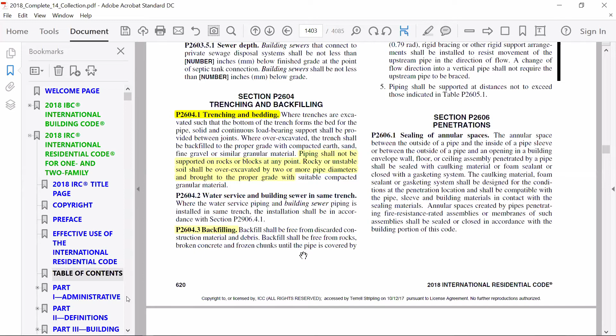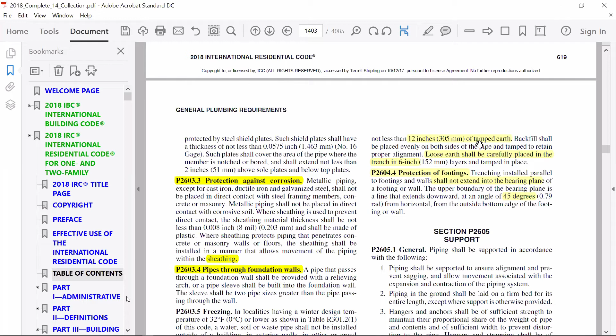So in other words, you put your pipe on the bottom of the trench. Maybe there's some good bedding down there, some gravel, some sand. Then you put 6 inches of nice loose earth, compact it, and then put another 6 inches of earth. That gives me 12 inches of tamped earth, right? That's what the code says. And then afterwards, then what can you put on that? Broken concrete, frozen things, beer cans, construction debris. The code doesn't care at that point because you've locked the piping in accordingly. That's all the code is stating, right?